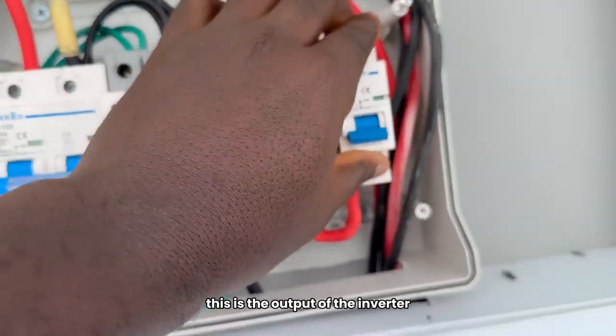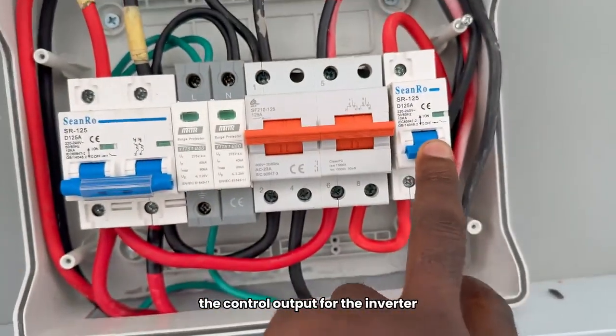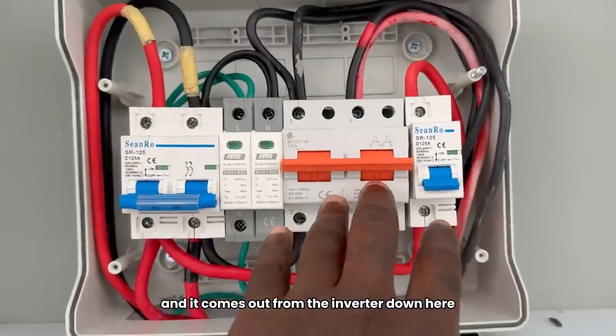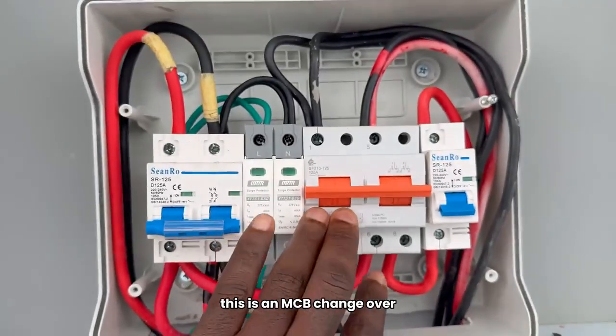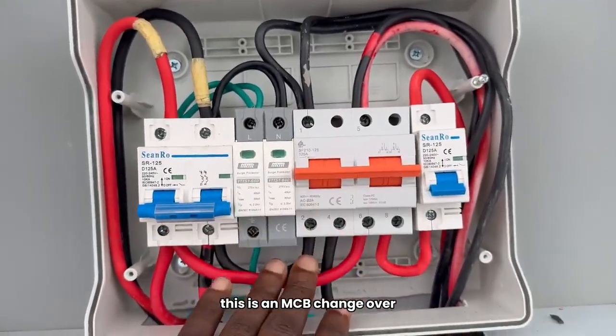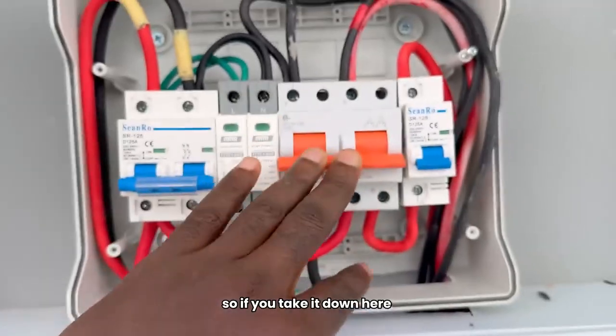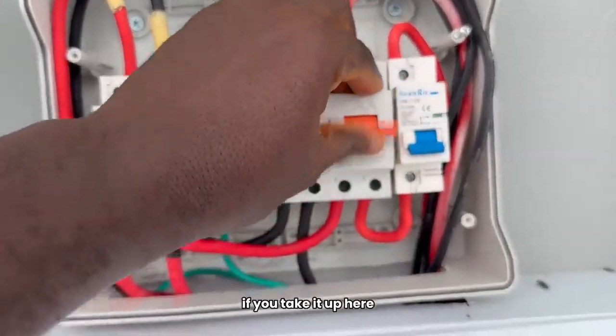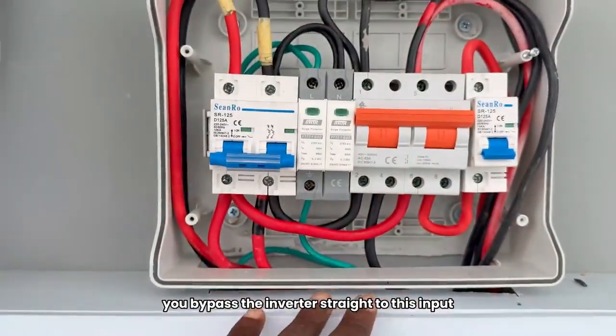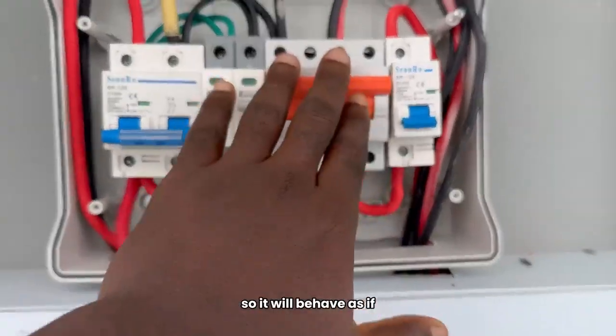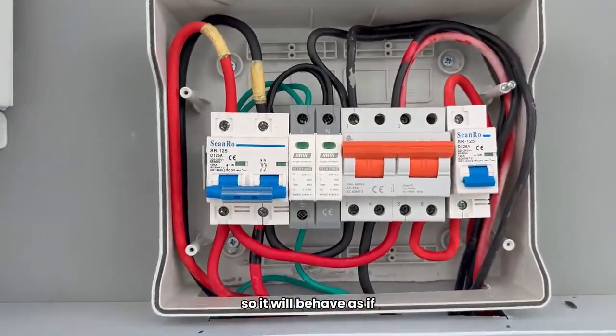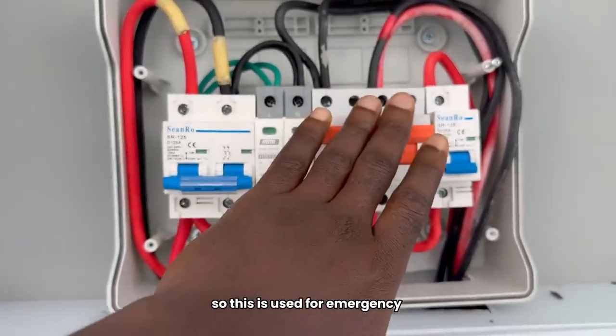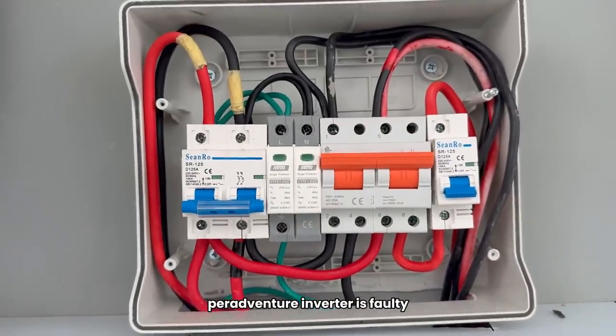This is the output of the inverter, the control output, and it comes down here to this MCB changeover. If you set it down here, it's on inverter mode. If you set it up here, you bypass the inverter straight to the input, so it behaves as if the inverter never existed. This is used for emergencies, if the inverter parameter is faulty, that's why we introduced this.